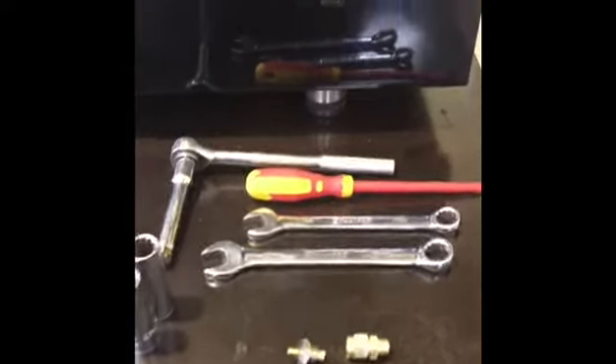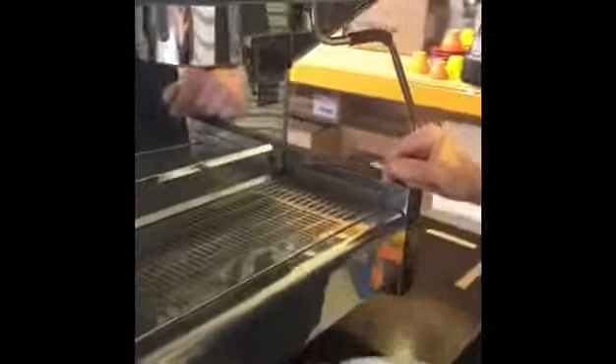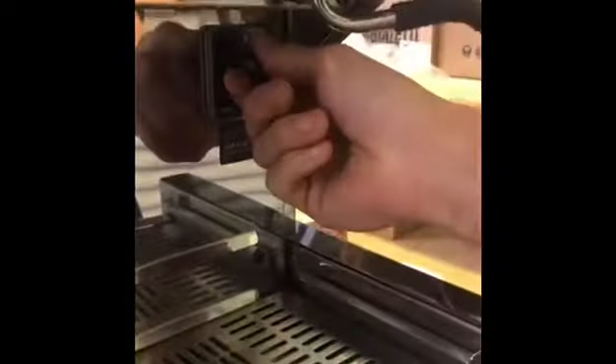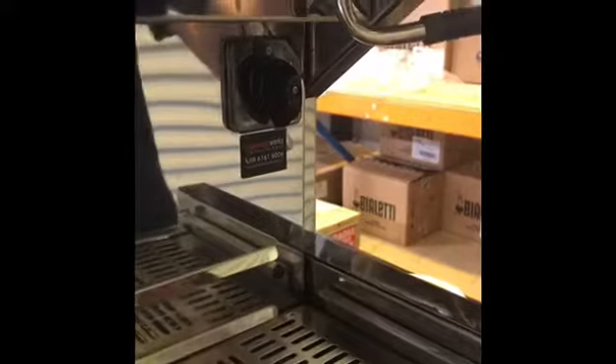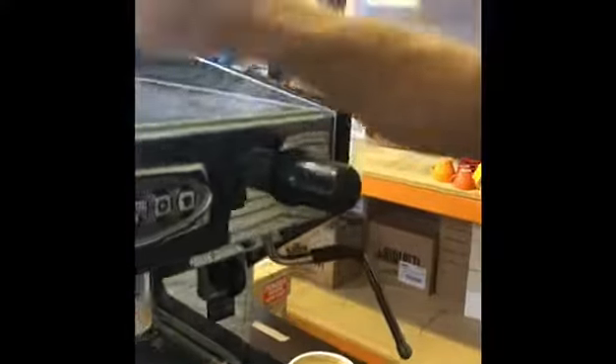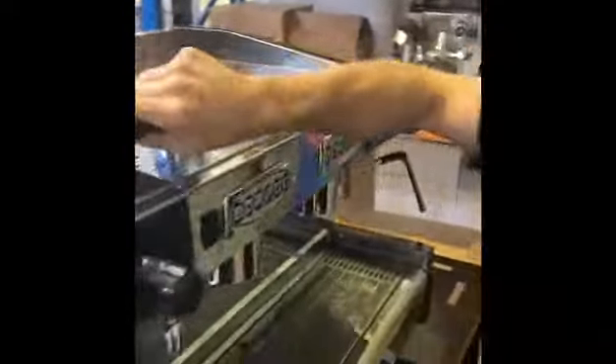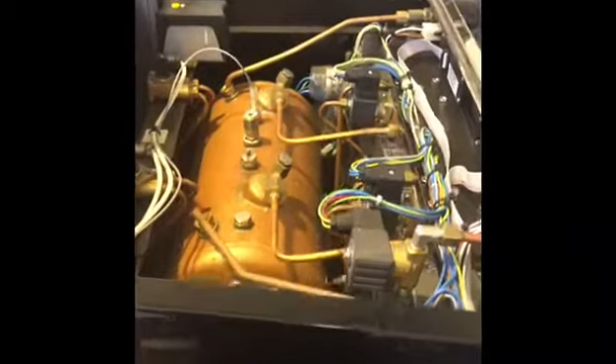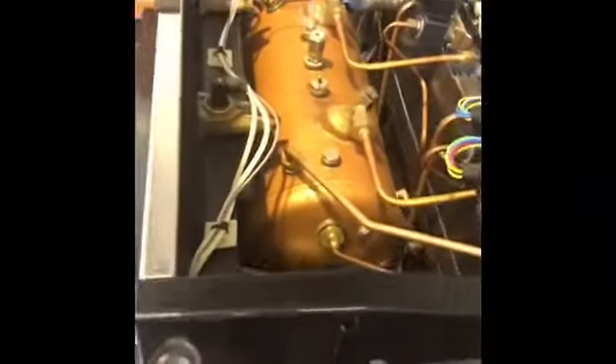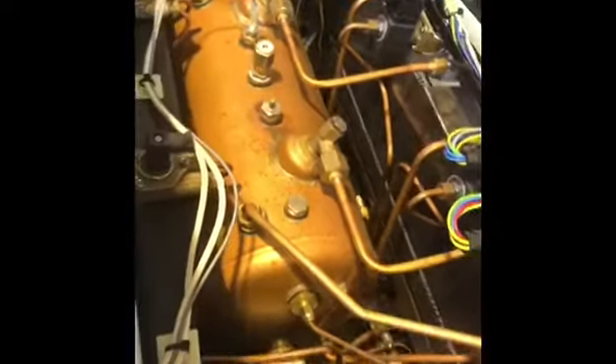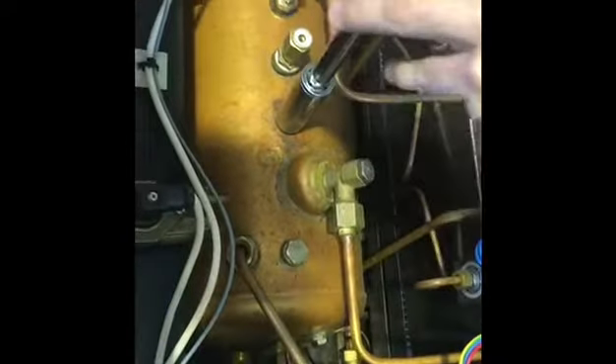machine off. It's very important on this portion of the service that the machine is turned off to 0 and the machine is completely de-steamed, as you're going to be working on a boiler which is under pressure. The top of the machine is removed. There's two screws on top which allow you to take off the top. And with your socket, just remove the anti-suction.